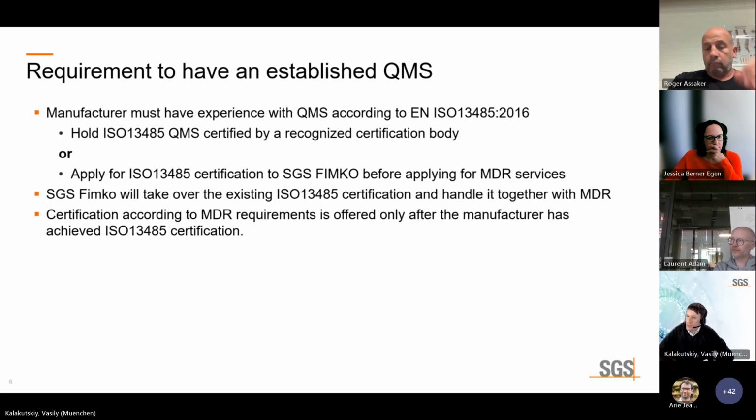Going further, what is necessary to apply for the notified body services of SGS FIMCO? The manufacturer must have experience with QMS according to the ISO 13485 standard. We know that not all notified bodies require that clearly. In our case, we have certain statistics that if the company has no experience with ISO 13485 and they immediately apply for both, for ISO and for MDR, they may get lost easily.